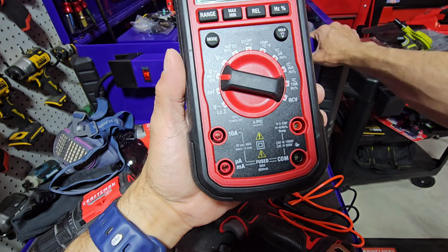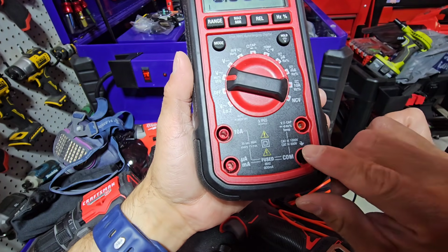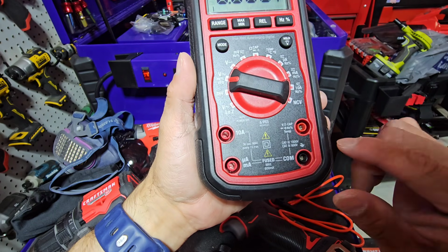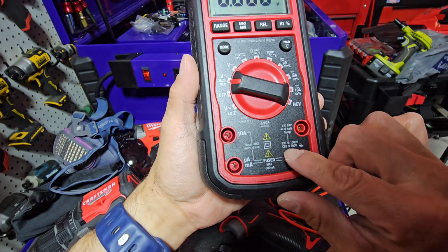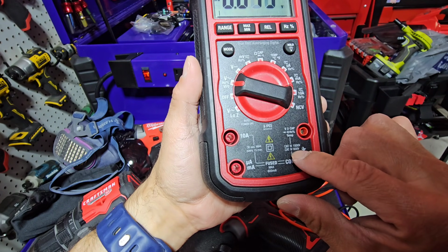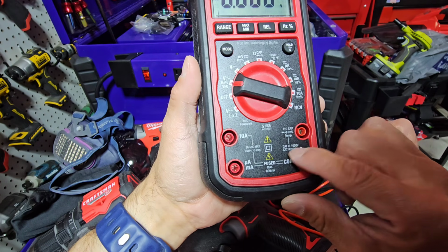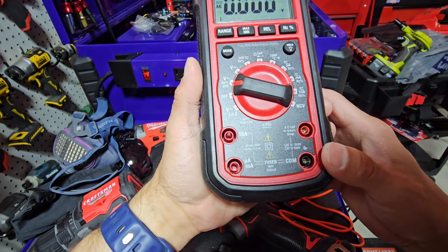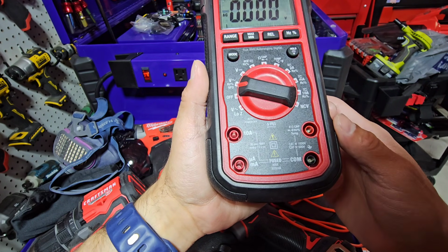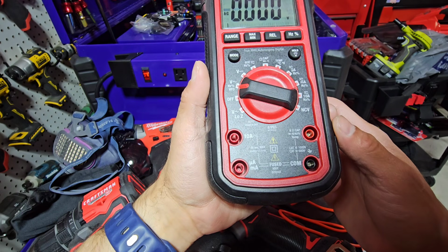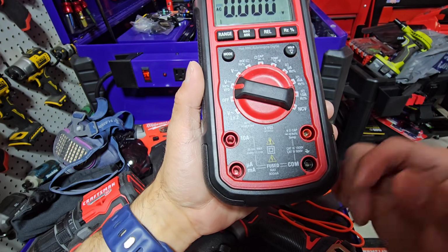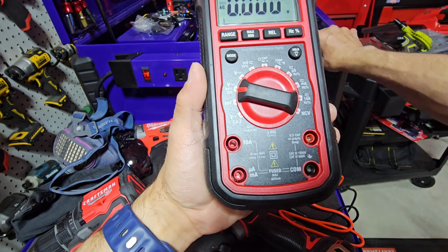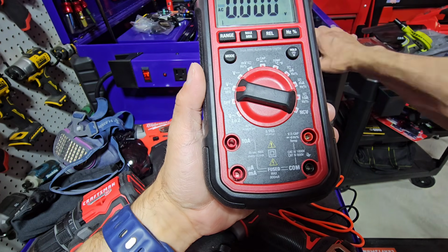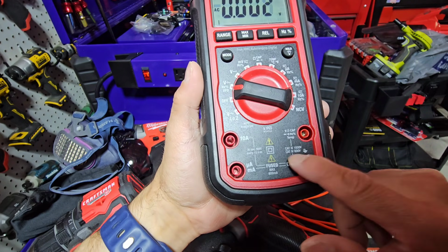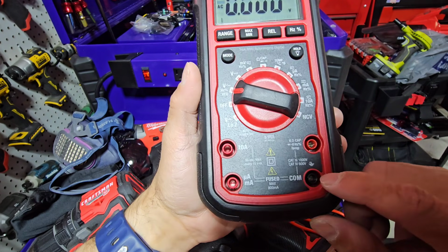For people with panel boxes outside, you want something Cat 4 rated, because of wet conditions. Something Cat 4 rated up to 600 volts - they do have Cat 4 1000 volt rated ones, but those are higher end brands, like a higher end Fluke, maybe the 378 FC version model, which is nice, or possibly the Fluke T6 1000 Pro. Those are good models.